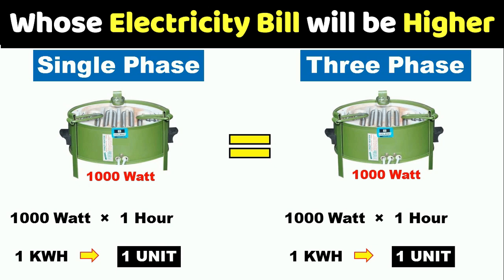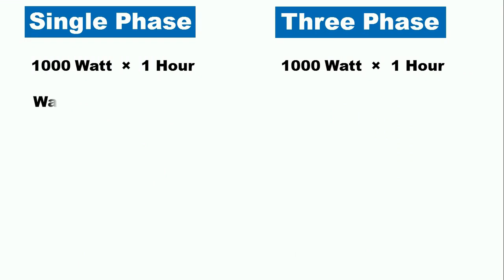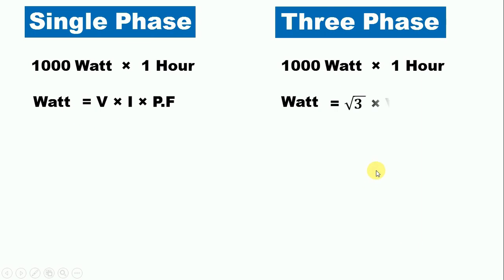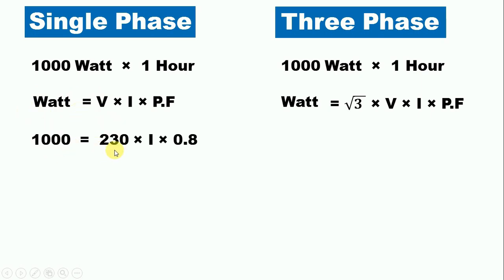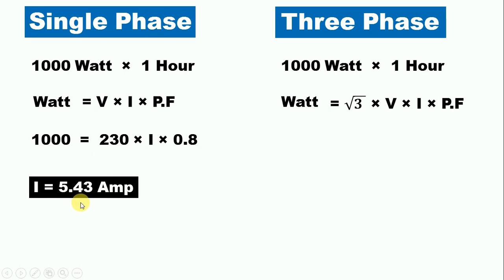To understand this concept, let us use the formula for power. For single phase: P = V × I × power factor. For single phase, power is 1000 watt, voltage is 230 V, power factor is 0.8, and we solve for current. When we solve this, the answer comes out as 5.43 ampere. It means this 1000 watt heater operating on single phase draws 5.43 ampere current.